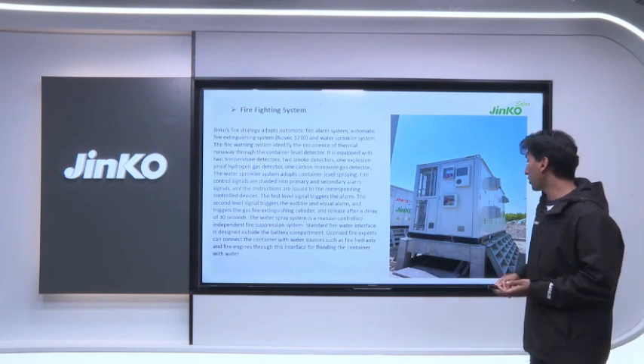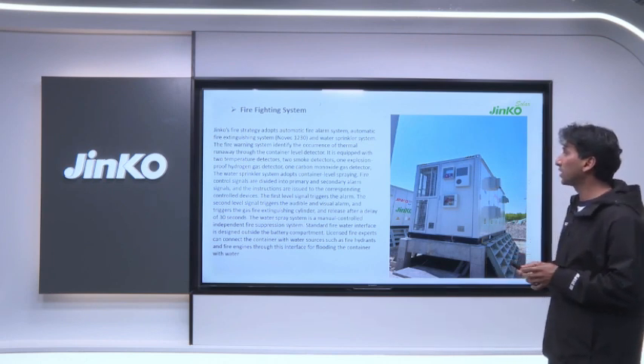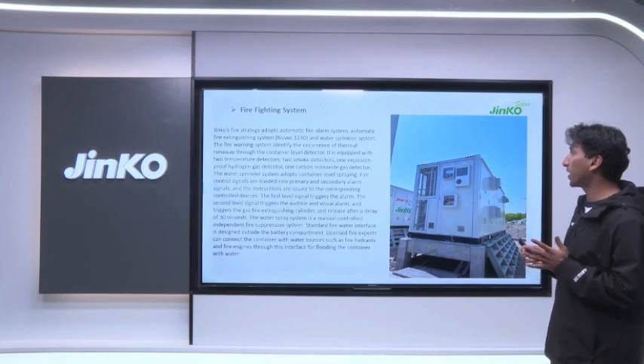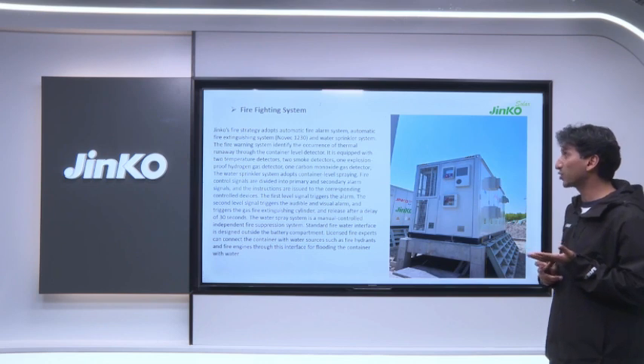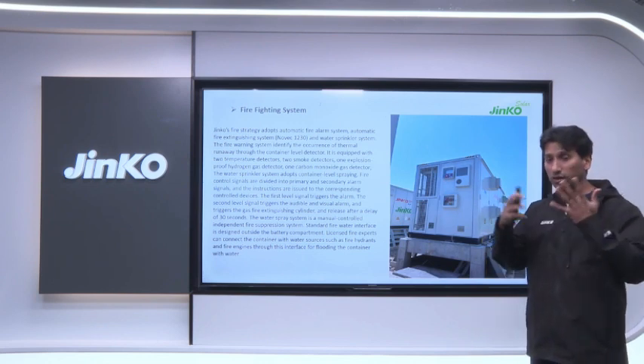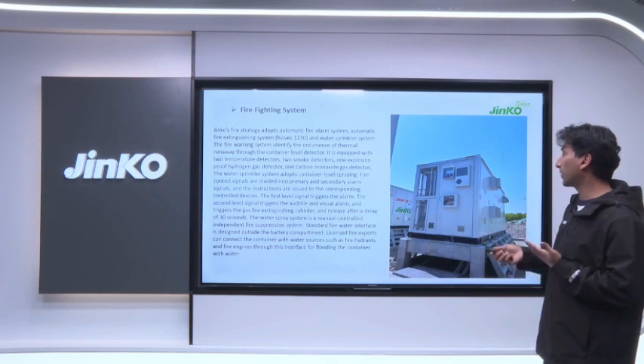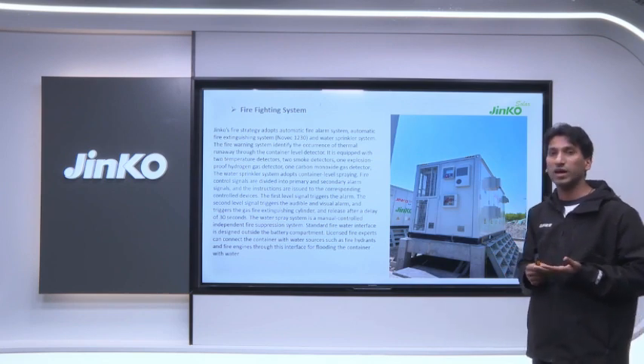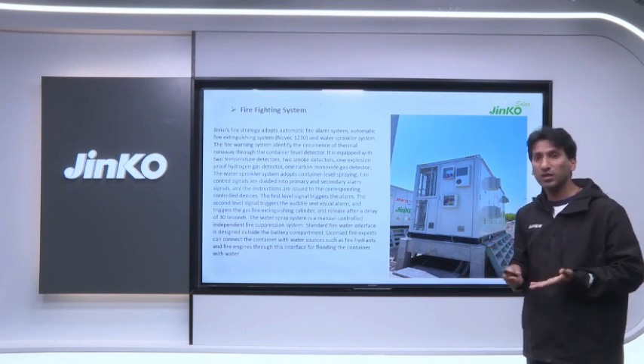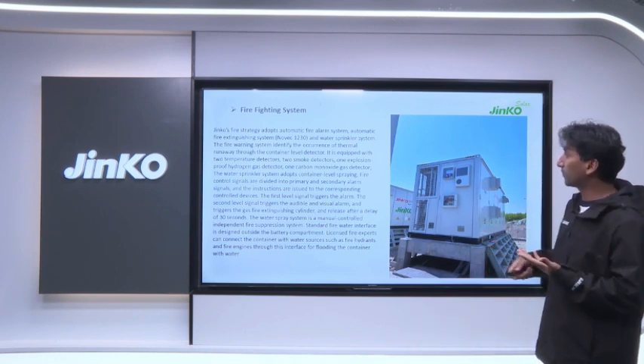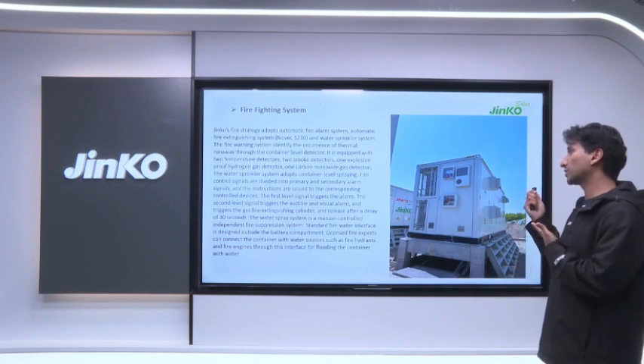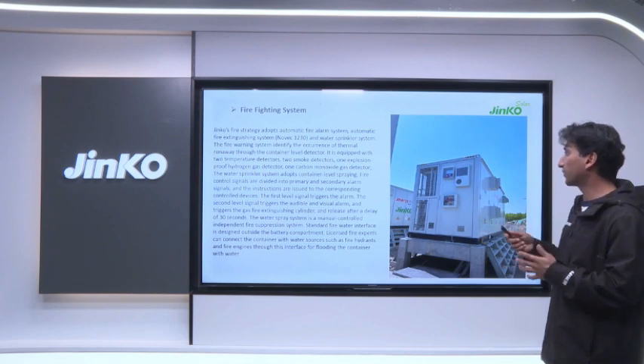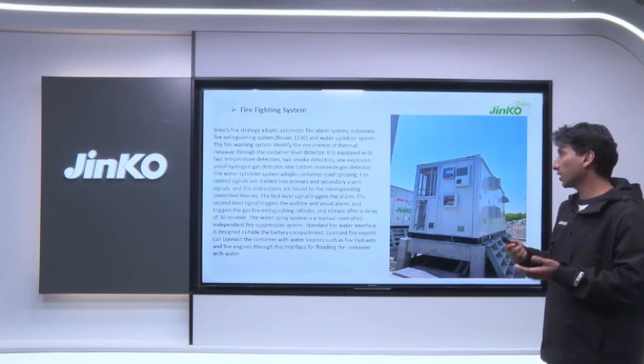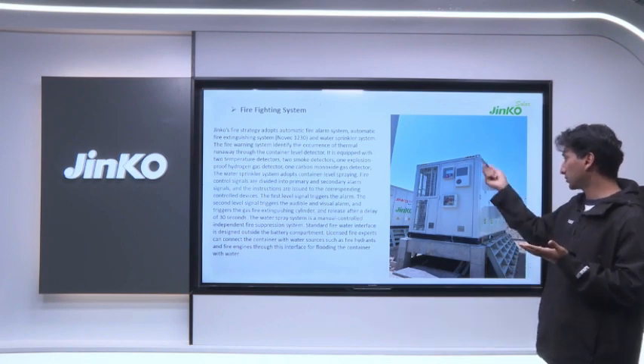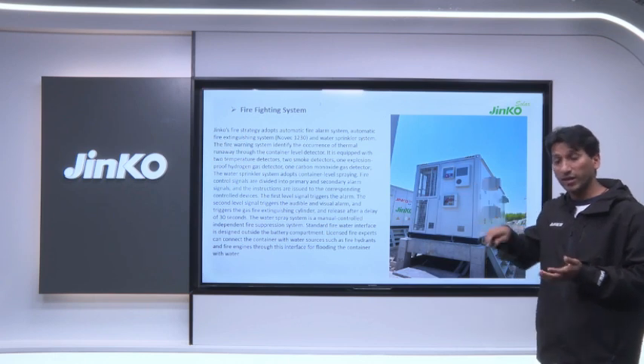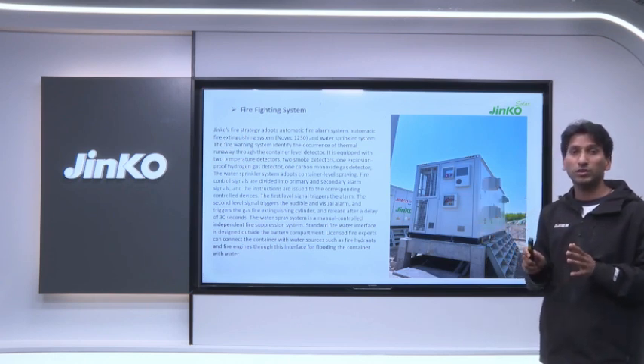Firefighting system. Each container has its own firefighting system, and it adopts an automatic fire alarm system, an automatic fire extinguishing system, and a water sprinkler system. It's a three-layer system. First we have the alarm system. If there is smoke or high temperature, the alarm will trigger. After the alarm is triggered, if the other sensors detect a fire, the fire extinguishing system will start working, and it will spray all over inside the container, and even inside the battery, depending on the design.